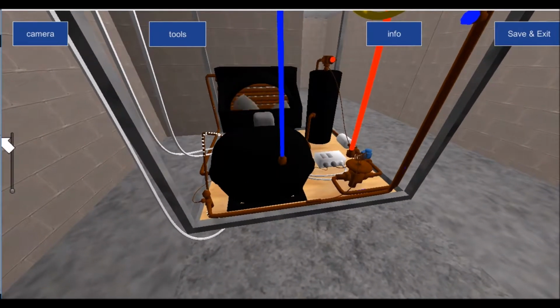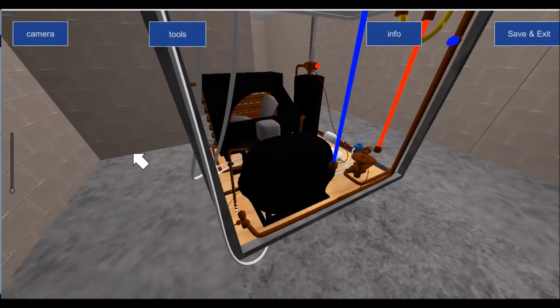Compressors come in many shapes and forms. So you have hermetically sealed and you have semi-hermetic compressors. The difference being a hermetically sealed compressor is completely sealed, such as this one. You cannot dismantle it. You cannot take it apart. You cannot do anything with it. So once it burns out, or seizes, or any kind of mechanical malfunction happens, you simply replace it, because it is not possible to strip it and take it apart.